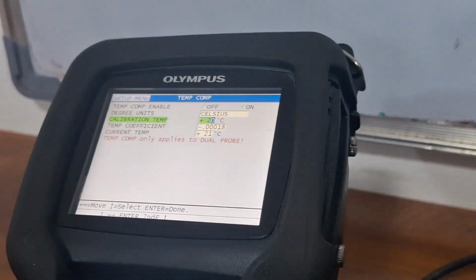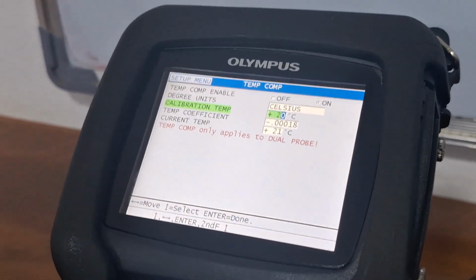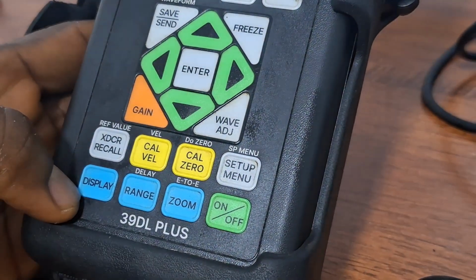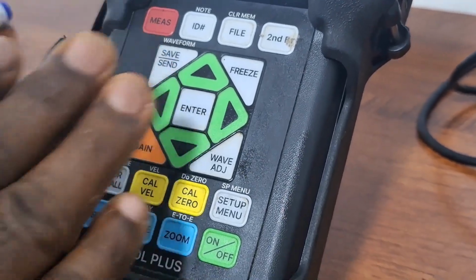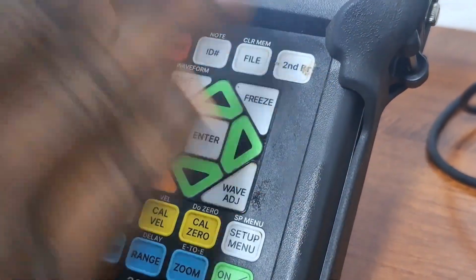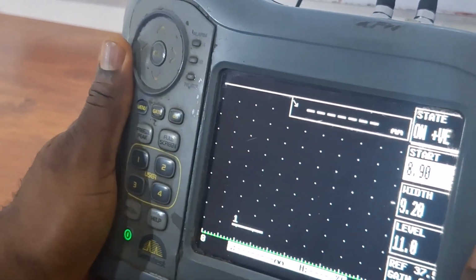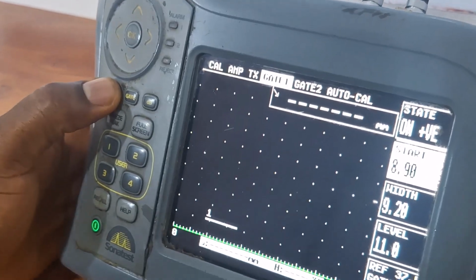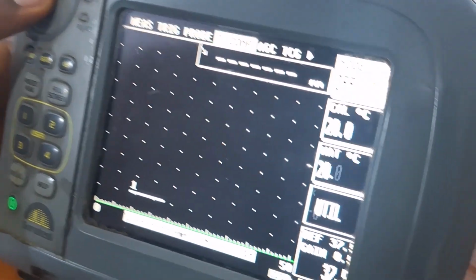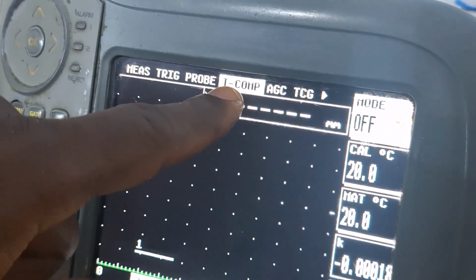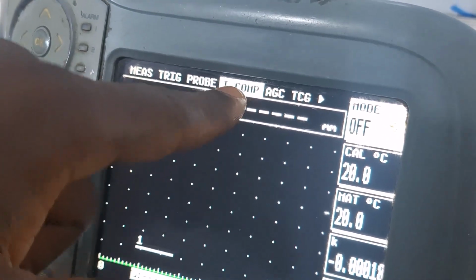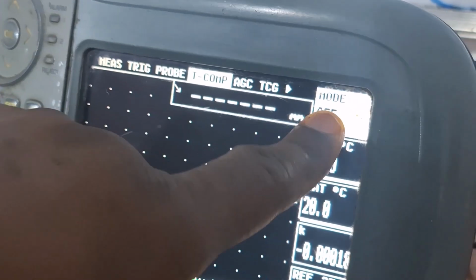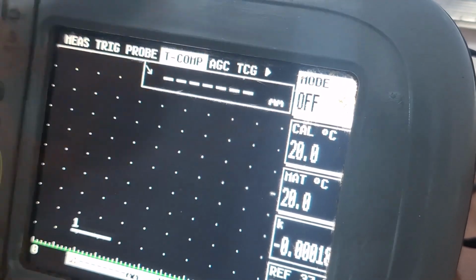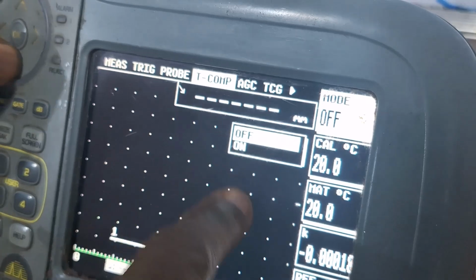Immediately you enter this value and you go to your measurements, and of course you are going to do your normal calibration, your setup and all that. So what this covers is just for your temperature compensation, but that does not take out the fact that you have to do your calibration and all for other things. For your Sonatest, if you go to your menu and you go to your measurement menu, you always see this T-comp. T-comp here is temperature compensation. As it is here now, temperature compensation mode is off. So if you want to compensate for temperature, you turn it on.